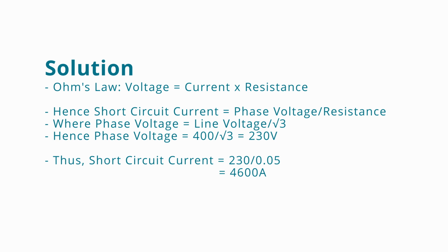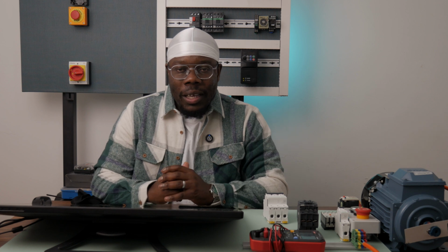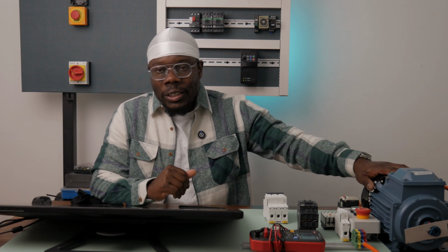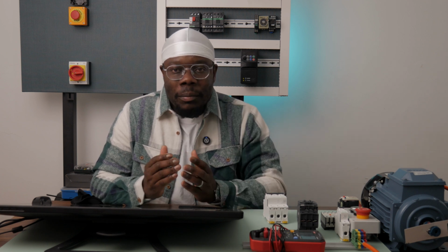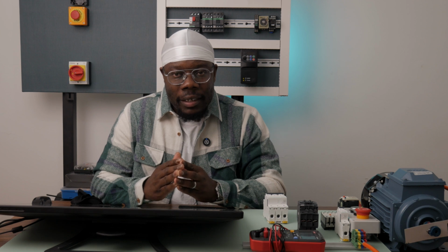So in a three-phase system, line voltage is 400 volts in this instance. And since our line voltage is 400 volts, our phase voltage is line voltage divided by the square root of 3, which is 400 volts divided by the square root of 3, which gives us 230 volts. So to calculate the short circuit current, we divide voltage by resistance. Short circuit current is voltage divided by resistance, which is 230 divided by 0.05, which gives us 4,600 amps. Now imagine 4,600 amps flowing through a small electric motor like this one that is designed to only take a maximum of 1.83 amps in normal operation. That sounds extreme, right? But that is what happens during short circuit conditions.